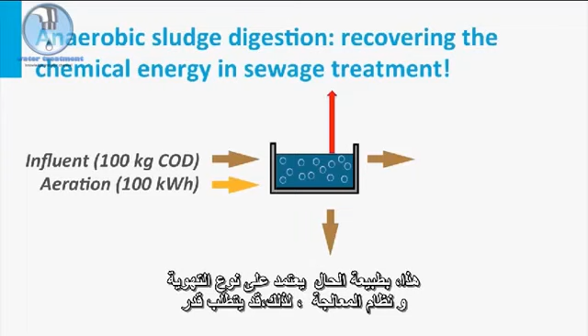When we start feeding the aeration tank with COD, we need about 1 kWh per kilogram COD that is fed to the aerobic reactor. Or, for 100 kg COD, we need 100 kWh, as depicted in this scheme. This, of course, depends on the type of aeration system and treatment process, so less energy may be required. In the aeration tank, all biodegradable organic carbon is oxidized to CO2, resulting in low effluent COD values.